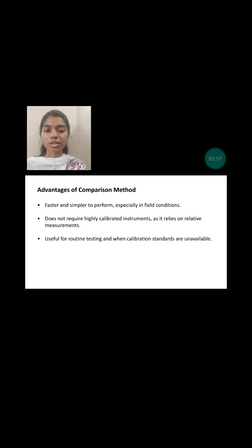Advantages of comparison method. The comparison method is faster and simpler to perform, especially in field conditions. It does not require highly calibrated instruments. It requires normal instruments as it relies on relative measurements. Useful for routine testing and when calibration standards are unavailable.